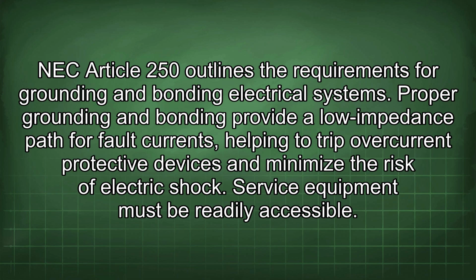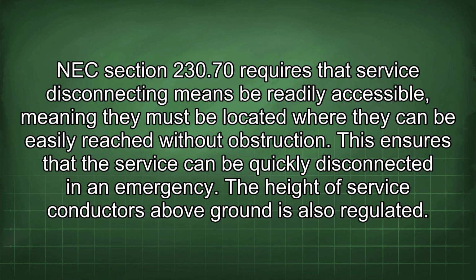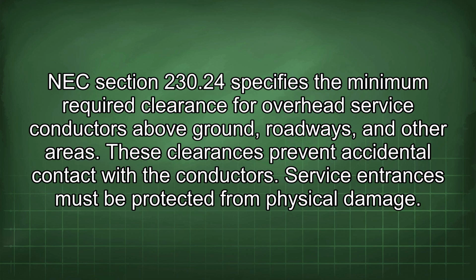Service equipment must be readily accessible. NEC Section 230.70 requires that service disconnecting means be readily accessible, meaning they must be located where they can be easily reached without obstruction. This ensures that the service can be quickly disconnected in an emergency. The height of service conductors above ground is also regulated. NEC Section 230.24 specifies the minimum required clearance for overhead service conductors above ground, roadways, and other areas. These clearances prevent accidental contact with the conductors.